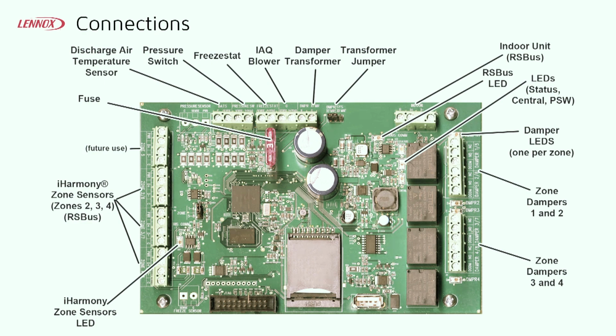One thing that can be confusing on these sometimes is you'll have a common, an NO, and an NC. NO and NC stand for normally open and normally closed. A lot of times what happens with guys is when they install these in a 3-zone, or if they have a 3-wire damper, where you have a common and a wire to open the damper and a wire to close the damper, they'll put the open on NO and a close on NC.